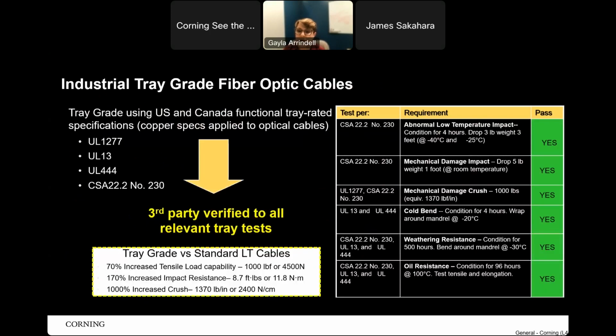There's another topic I'd like to introduce, what they call tray grade fiber optic cables. In North America, US and Canada, this is a specification that was generally designed for copper cables, because of electromagnetic interference issues with copper. But with fiber cables, we were able to take some of the relevant specs in these UL standards for mechanical, temperature, and crush testing, and apply them to our industrial tray grade fiber optic cables.